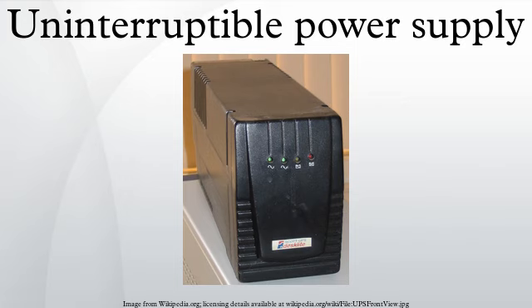Auto-transformers can be engineered to cover a wide range of varying input voltages, but this requires more taps and increases complexity and expense of the UPS. It is common for the auto-transformer to cover a range only from about 90 V to 140 V for 120 V power, and then switch to battery if the voltage goes much higher or lower than that range.